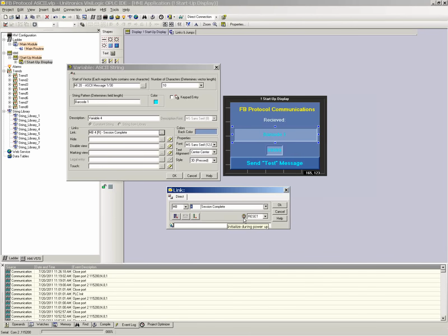It's more of a legacy bit. The older 120s, say, or the 200 series, require that you refresh the screen before a variable string will update. So if we sent hello and then webinar on, say, a 200 series controller or a 120, you would have to manually refresh the screen for it to actually update and show that the new message has arrived.